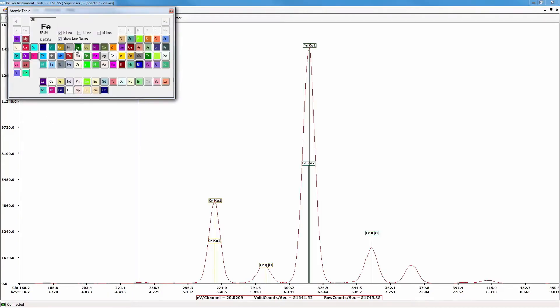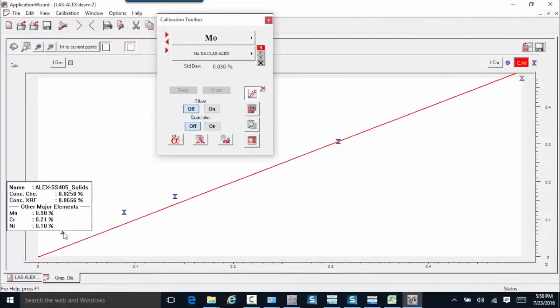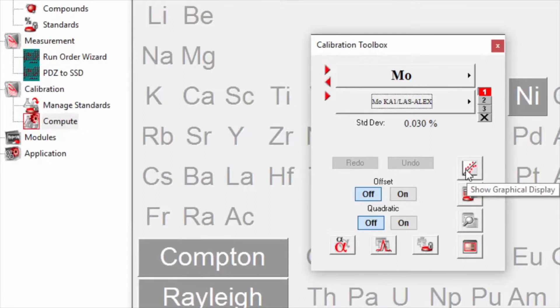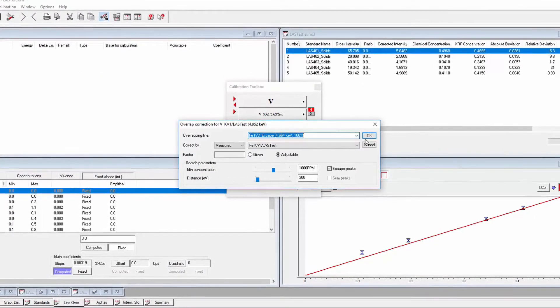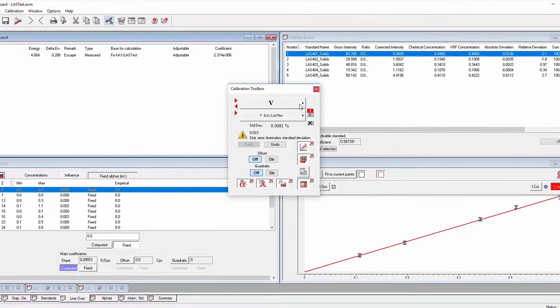Spectrum display, report generator, grade table editor, limits editor, and multi-user support are features of Bruker Instrument tools PC software. Optionally available EasyCal PC software supports user-defined and site specific empirical calibrations. EasyCal incorporates Lucas-Tooth modeling and provides comprehensive tools for inter-element corrections. The instructional wizard walks the user through EasyCal's calibration process using a graphical interface.